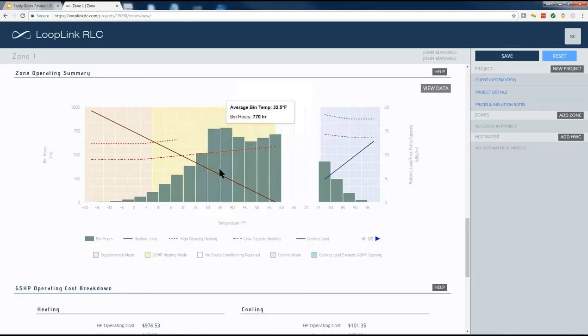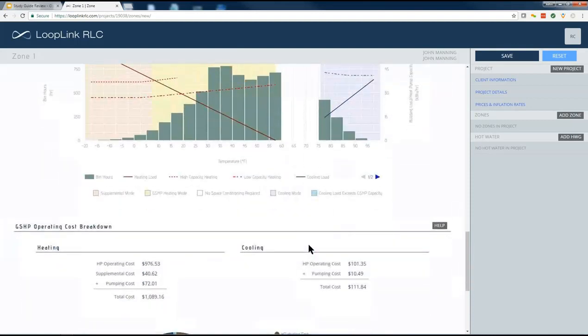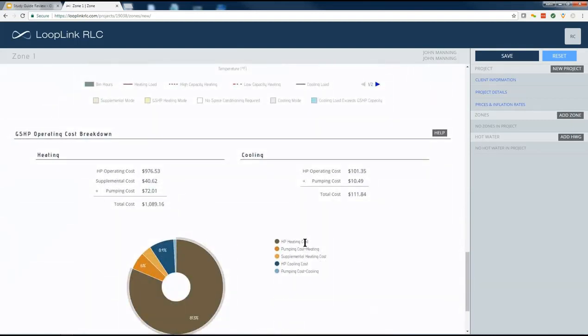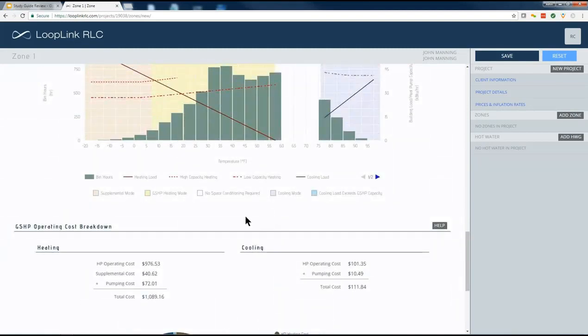So you can see all these hours here. The low line here is part load heating capacity. So all the hours to the right of this intersection, that's all part load heat pump operation. Everything between this line and this line is full load heat pump operation without supplemental, and everything to the left here beyond that, all of these hours are heat pump plus supplemental operation at the same time. So that kind of gives you an idea of what the weather looks like and what that all means in terms of heat pump sizing relative to runtime, relative to operating costs, which is really what we all are most concerned with.